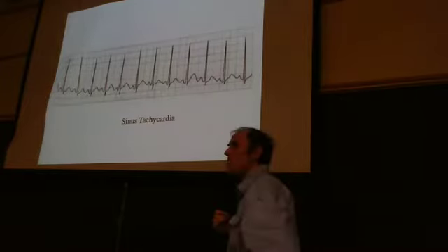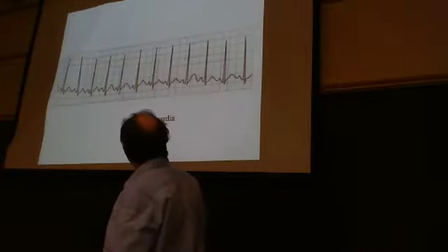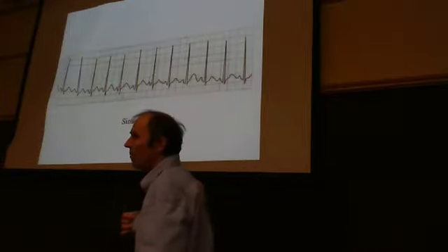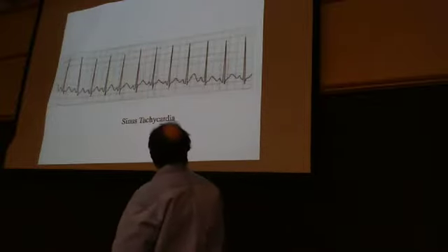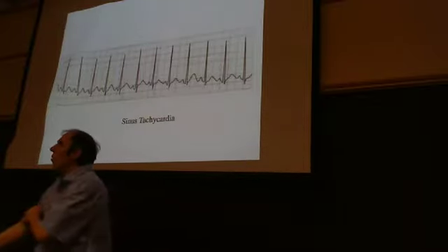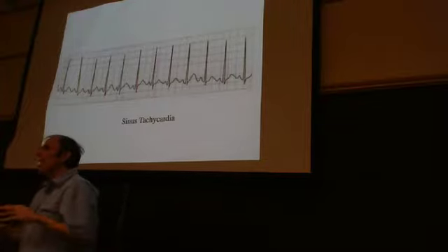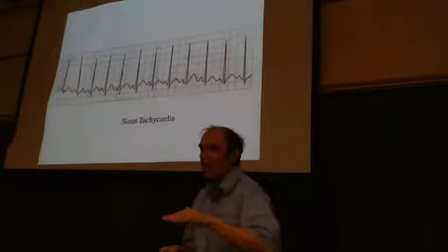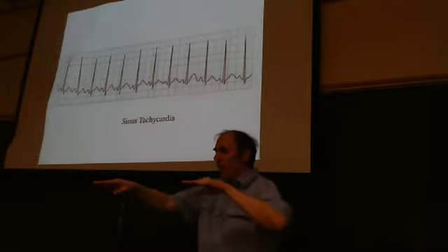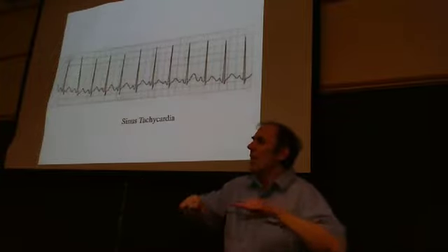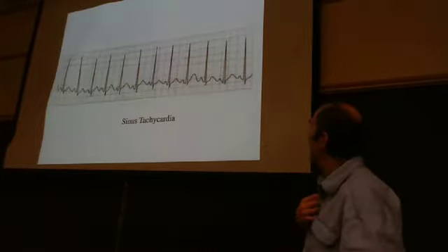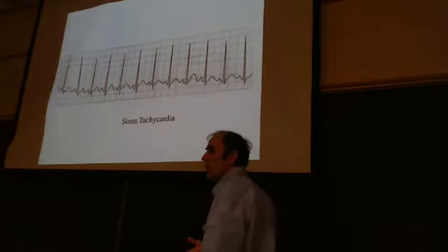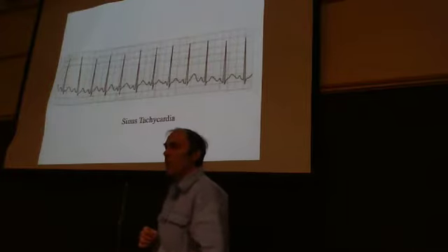With this graph, the baseline moves up and down. Is that just random chance, or does the heart at times become tetanic? I would say that is probably electrode motion or something. I think that's artifact. That's why a lot of times you'll have your measuring device AC coupled to get rid of baseline drift, but that's essentially baseline drift, and I don't think that has any information in it. I think it's an artifact basically.